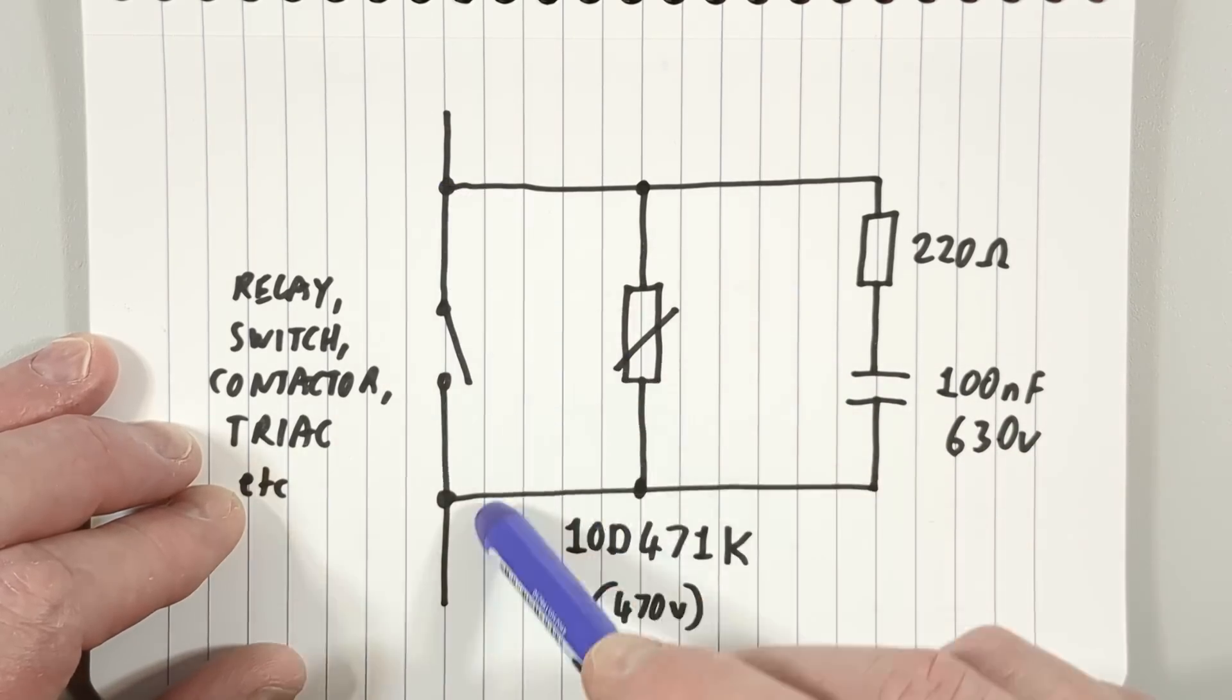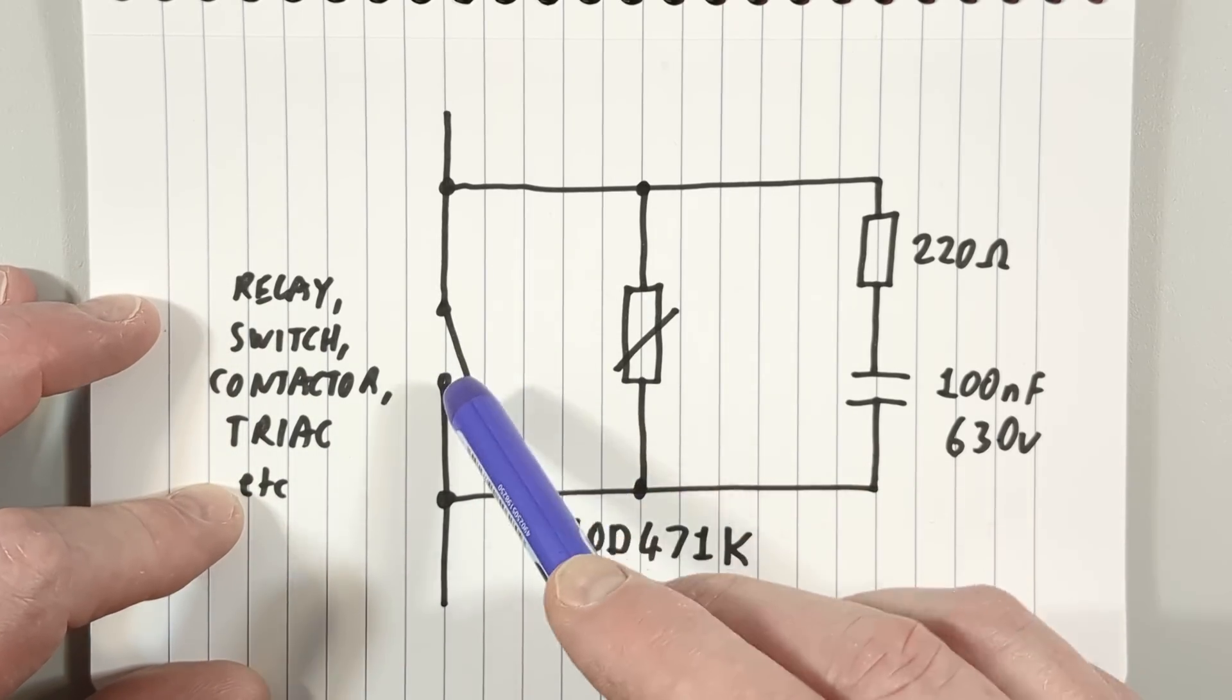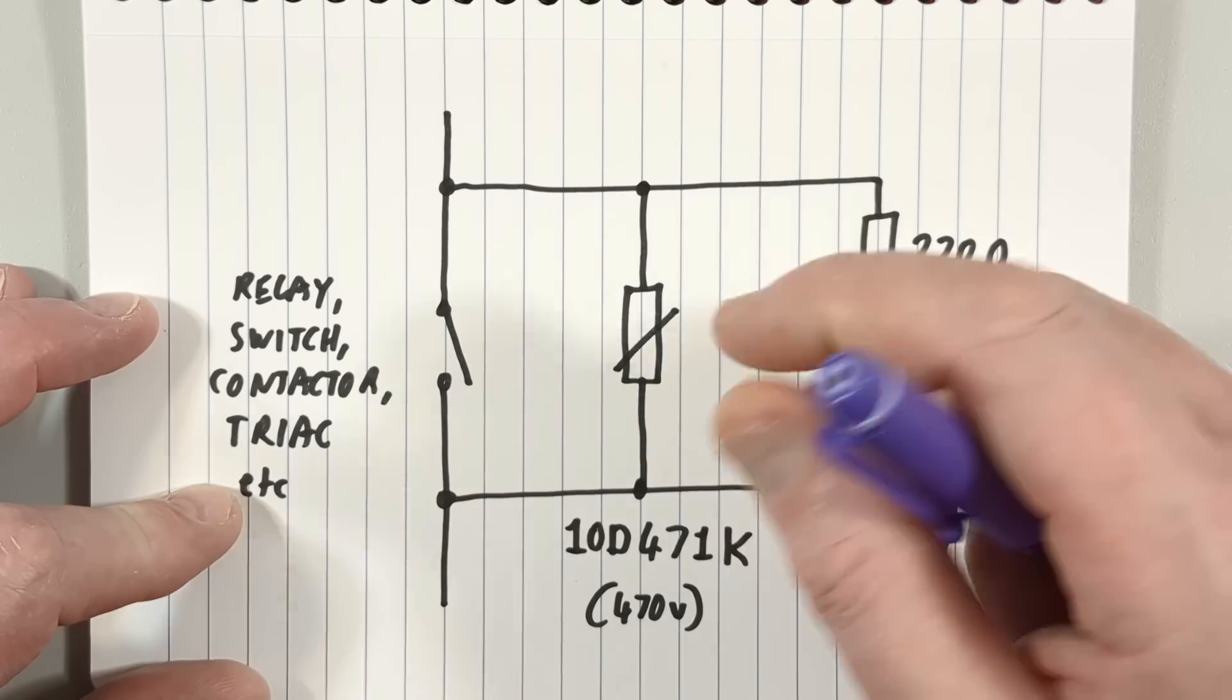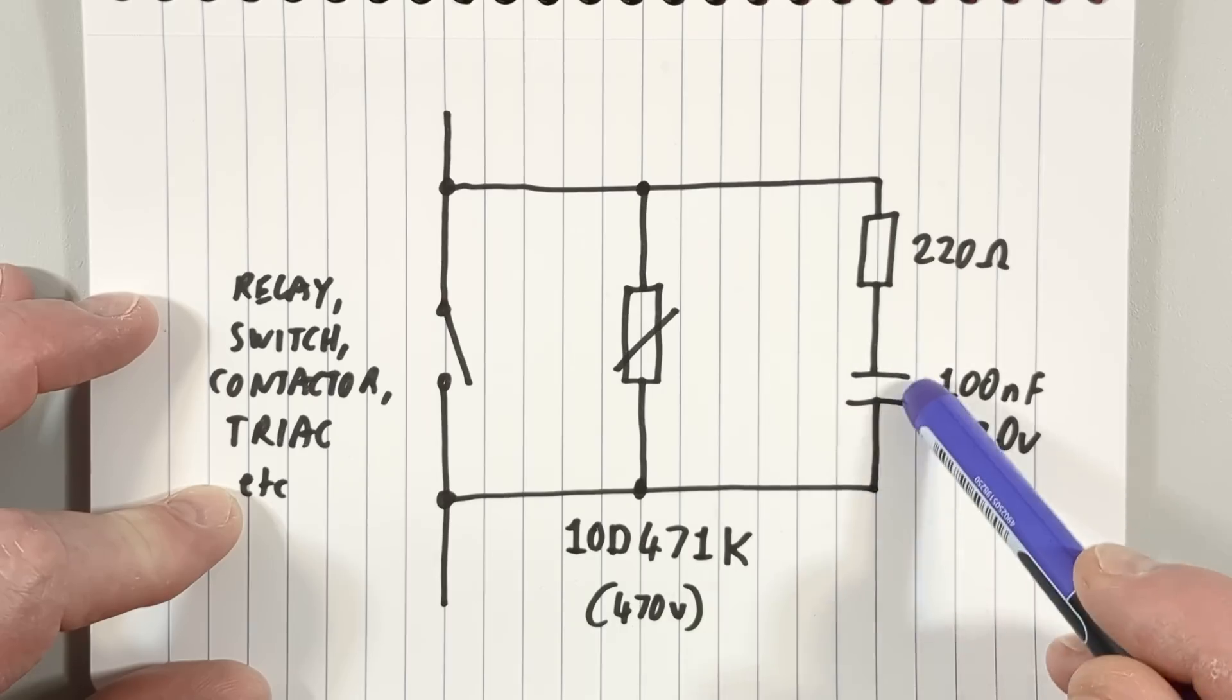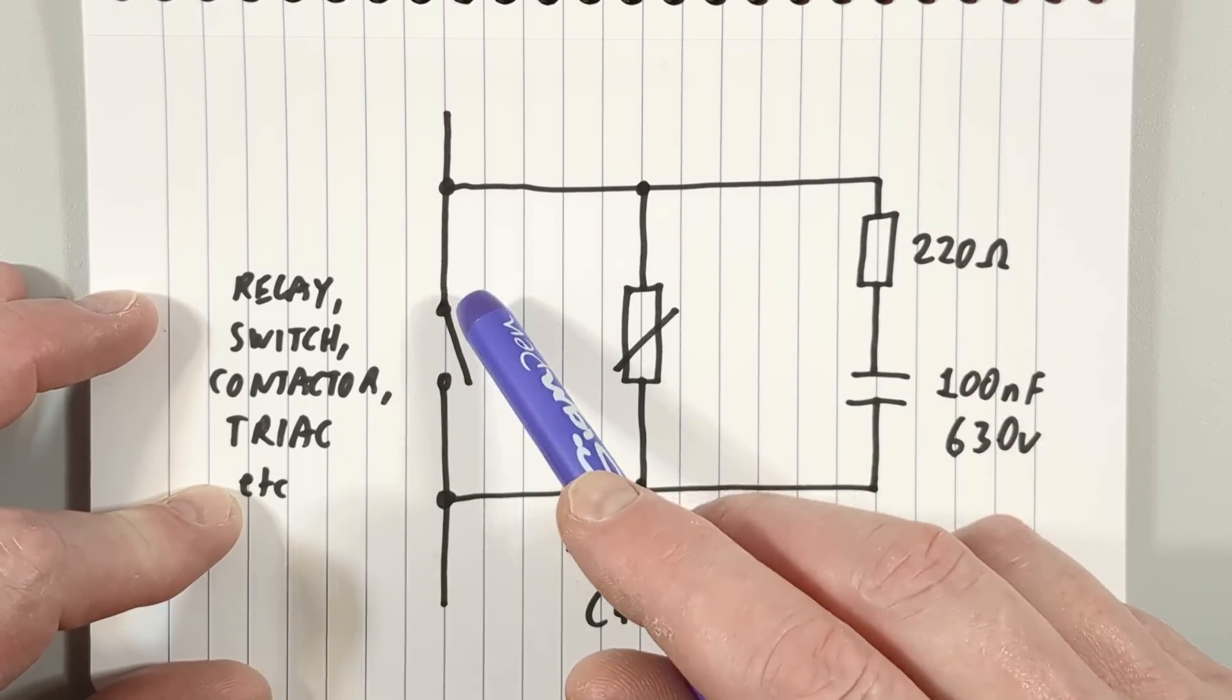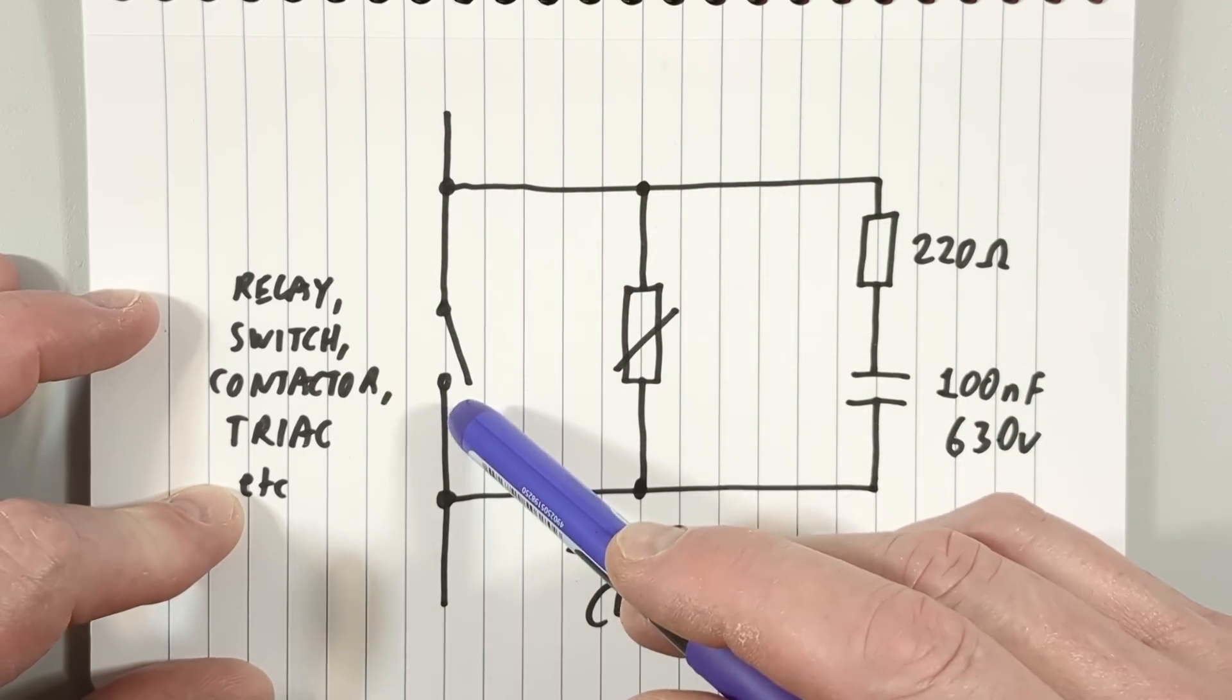When you put it across a contact and the contact opens, you can get a slight arc drawn. That arc causes high frequency electrical noise across either side of the switch. Because these capacitors are very good at passing electrical noise, the capacitor shunts that and actually controls the arcing, reducing the amount of arcing in the contact.